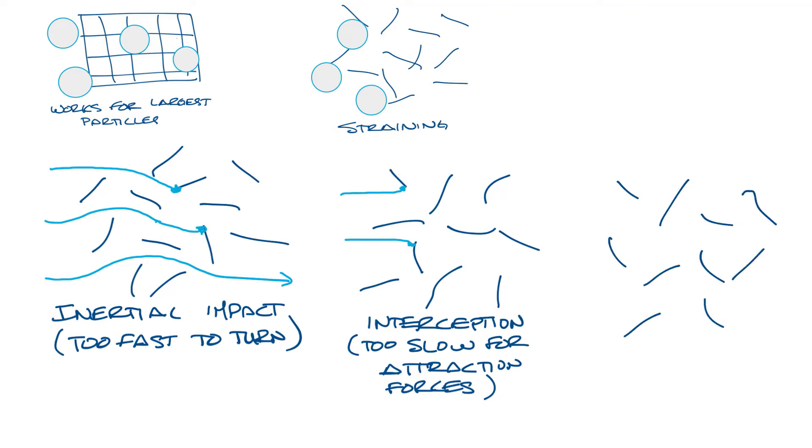Now for the smallest particles, these particles that are so small that the motion of the air molecules around them can make them bounce around as they travel. So they move in a motion kind of like this as the air knocks them around. This is called Brownian motion. And since they're moving all around, they also get caught in the fibers. This is called diffusion.